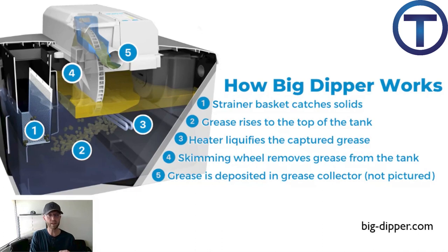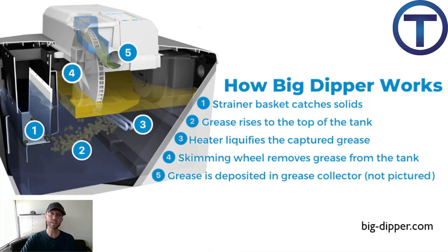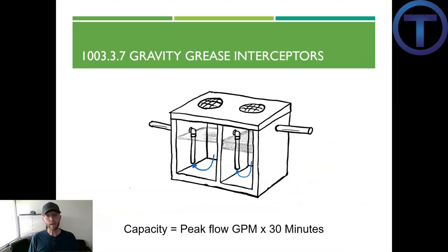What this device does is bring the fluid into the first chamber where a basket strainer catches all the solids — any food waste is caught there first. Then grease and liquid flow into the main chamber where the grease rises to the top by gravity, but it's encouraged and liquefied by a heating element, making it really liquid on top. From there, a skimming wheel pulls that grease off the top and puts it into a separate grease collector — an exterior tank you can use to haul the grease off. This is a great improvement over the gravity type where you just let the grease float and get rid of it periodically.